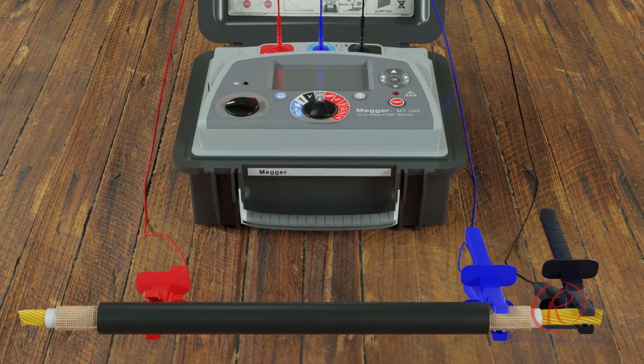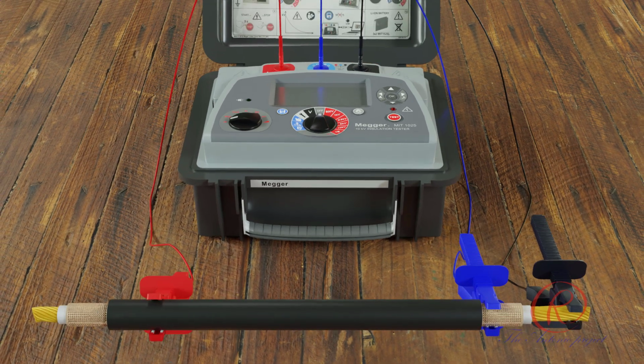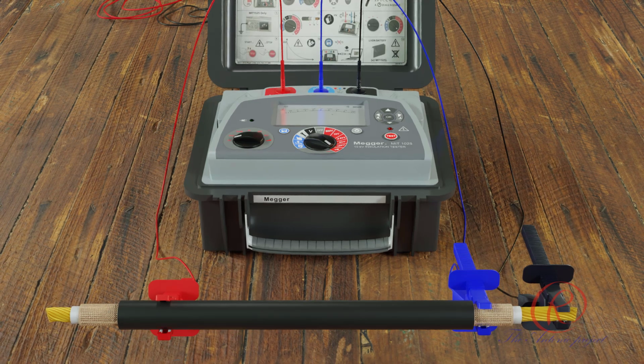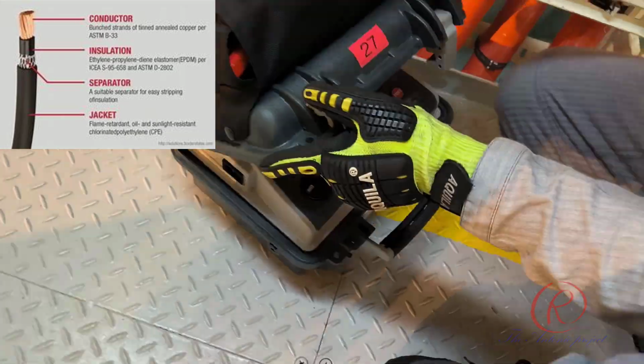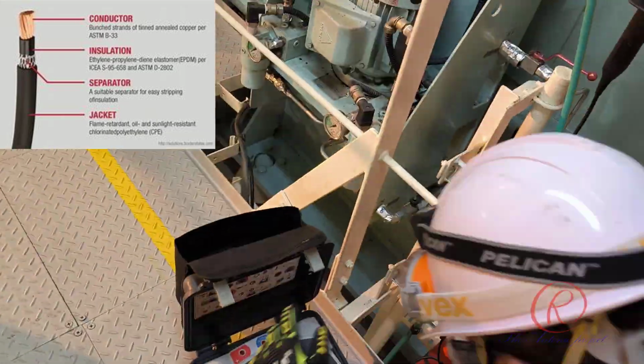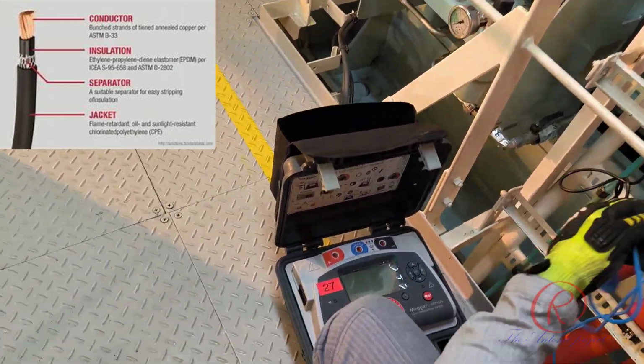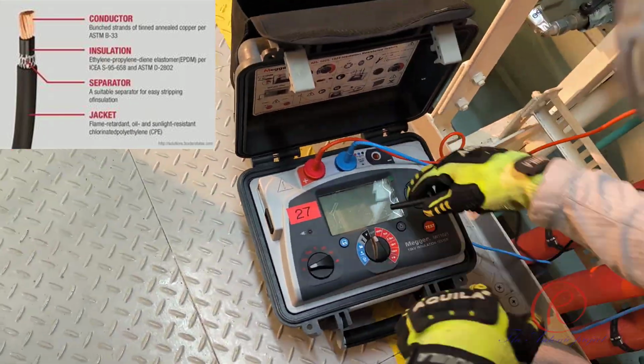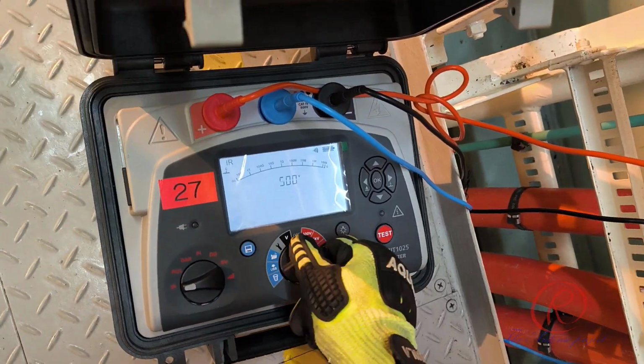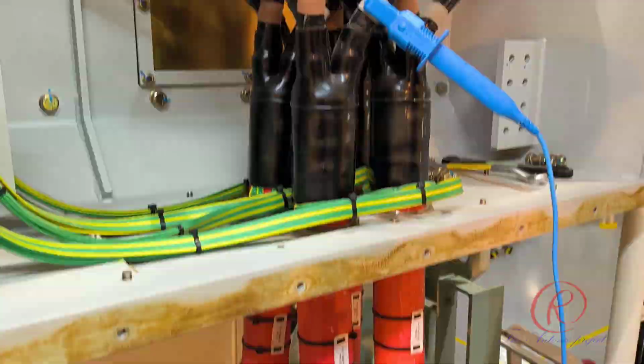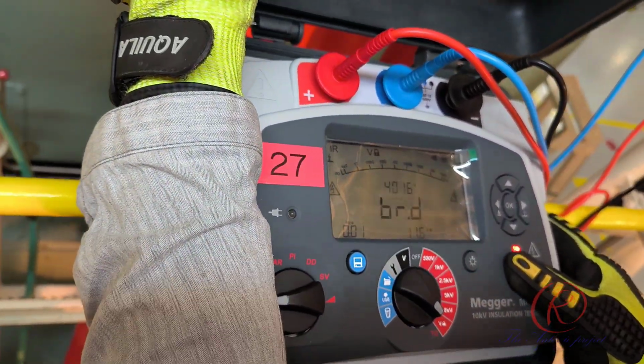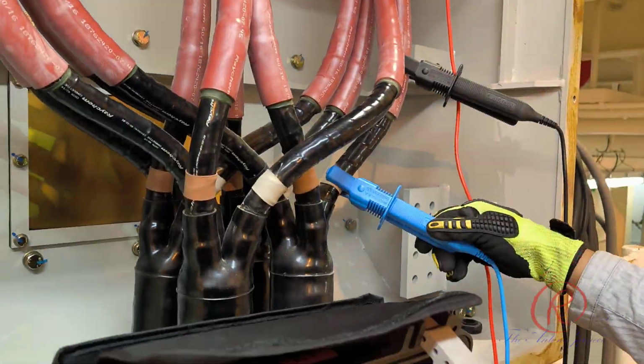A bare wire may be bound tightly around the insulation and connected via the third test lead to the guard terminal G. The guard terminal is at the same potential as the negative terminal. For measuring high voltage cable insulation resistance, MIT1025 uses the test voltage 6.6 kV DC. The purpose of this measurement is for detecting any defect on the cable insulator, any leakage or grounding on the cables.